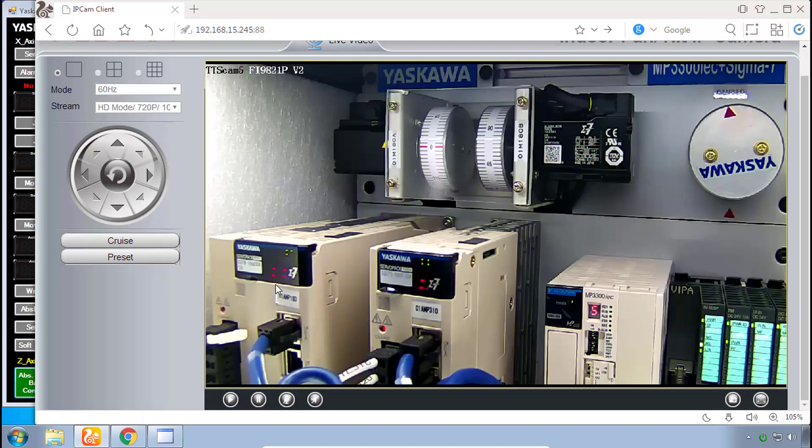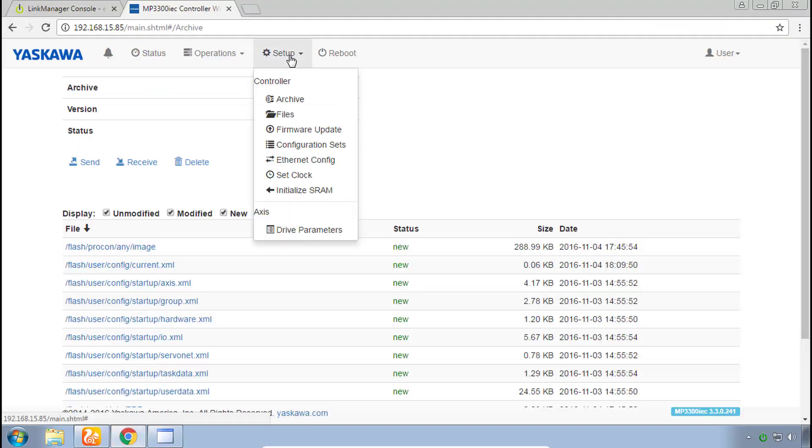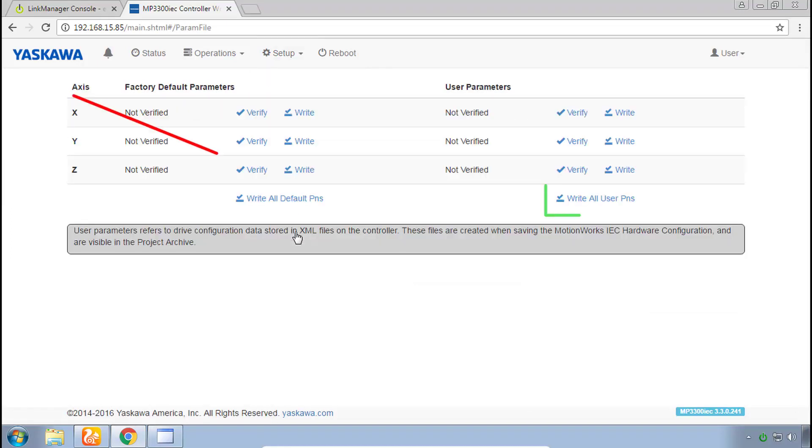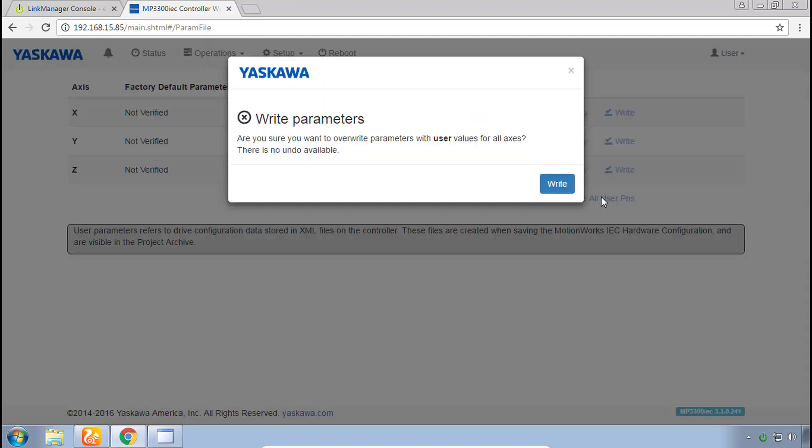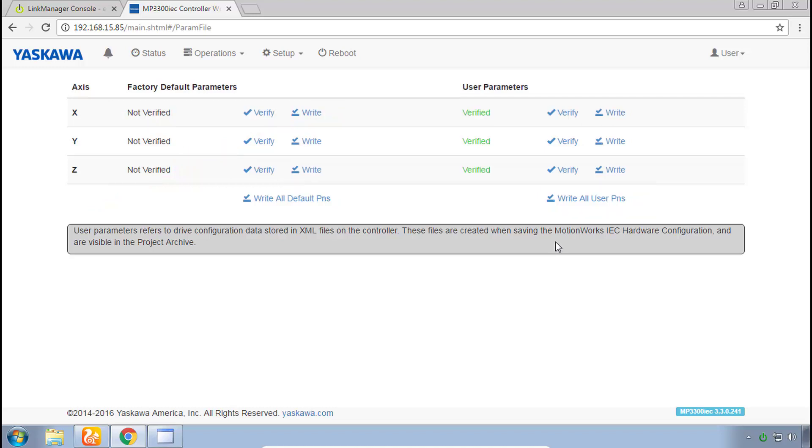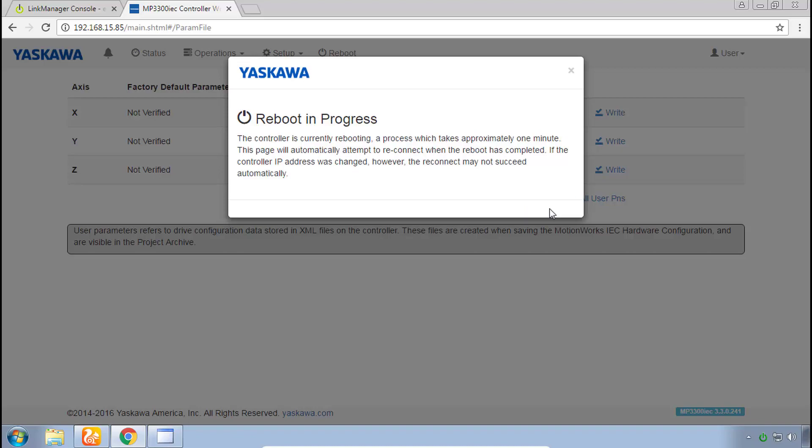Back to the web UI under Setup again go to the bottom Drive Parameters and on the far right here click Write All User PNs and then confirm with Write. That writes all the parameters and reboot again to make those active so reboot, reboot.